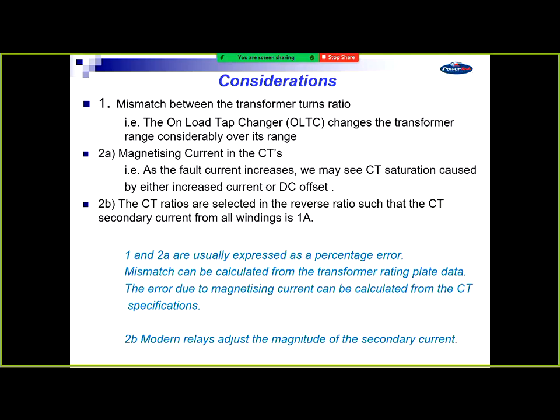Actually, we select those in the reverse ratio. It doesn't matter now. With the old electromechanical relays, you had to select ratios of CTs to try and keep that current balanced. You didn't have that perfect 10-to-1 transformer. You had a 10.5-to-1 transformer, so you didn't get CTs matched like that. For the zero sequence, we used to have to connect the deltas up in CT, so we ended up with CTs not with a 1 amp secondary, but with a 1 on square root 3 amp secondary. So we used to have to take those sort of CTs. So it was very complicated with the old electromechanical.